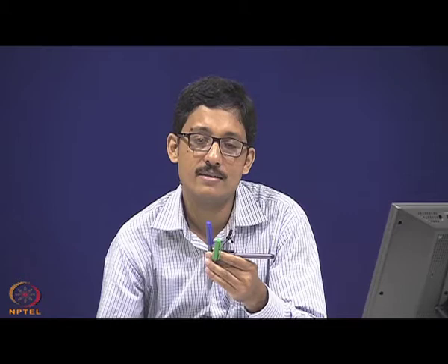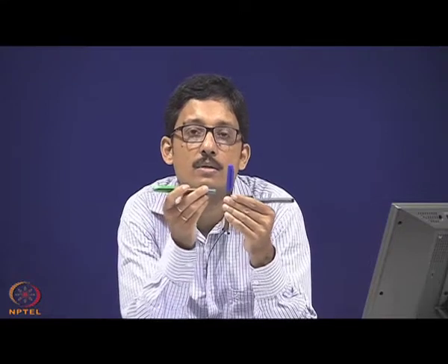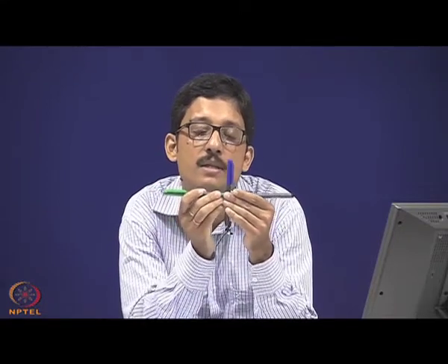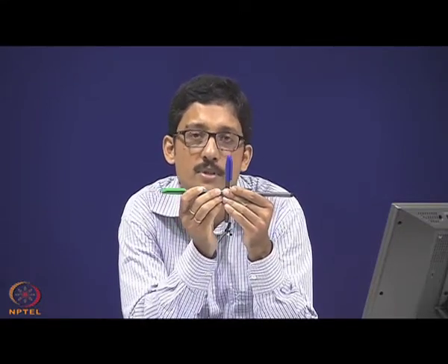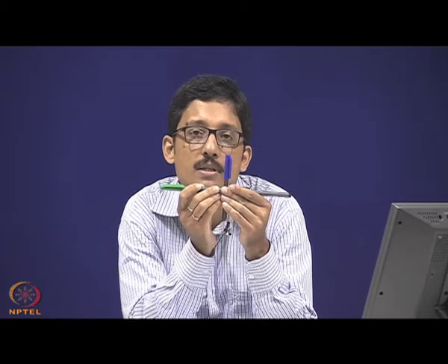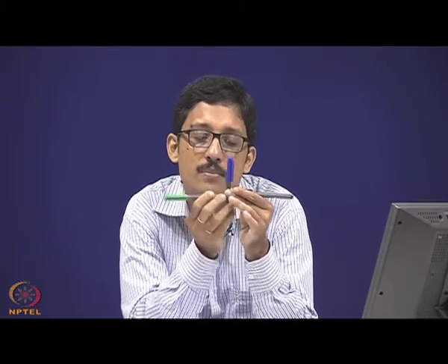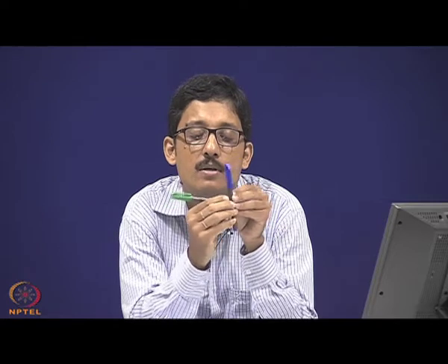So, in this case, the absorption signal along with the emission signal will be there. I mean this signal will be contaminated with the absorbance signal as well as the emission signal. So, in order to get rid of that, we keep the detector at 90 degrees with respect to the excitation source to minimize scattering and avoid the excitation source.